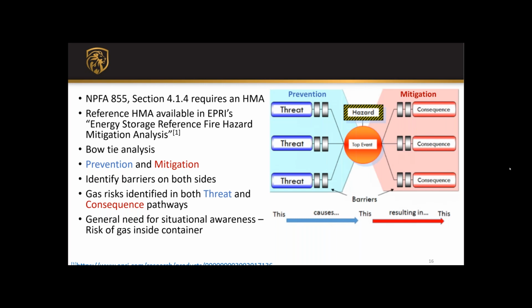We'll begin with the hazard mitigation analysis. First and foremost, NFPA 855 requires energy storage systems to be presented with a hazard mitigation analysis. There's a reference hazard mitigation analysis available in some of EPRI's products. It looks a bit cut off on my screen, but there's a link at the bottom—you can get the slides afterward and find out more. They've taken an approach using a bow tie analysis, a specific type of hazard analysis.